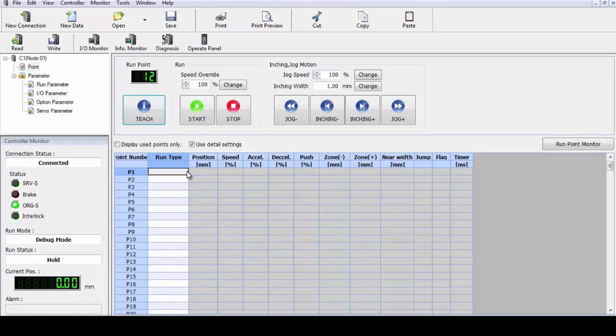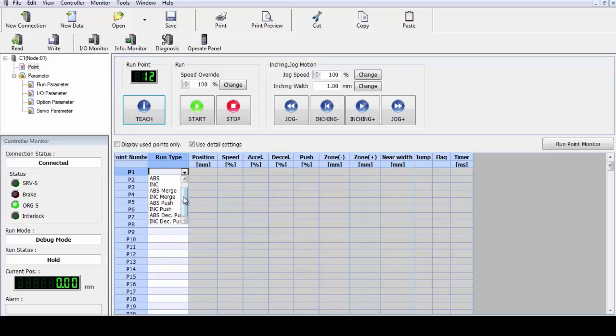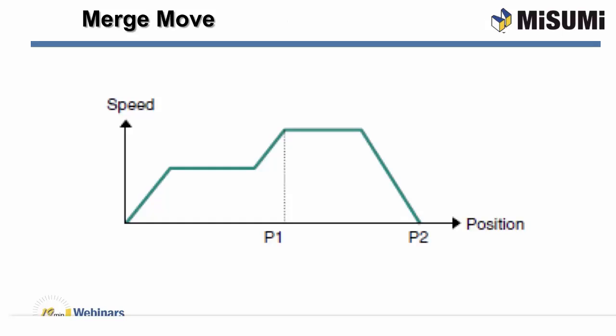Let's go back to our program window and let's take a look at a couple of things we can do. We're going to set up a couple of different run types. We have two different types of run modes that we can be. We can make incremental or we can make absolute moves. If you go down through here, you click on run, it shows all the different moves that are available. Now, on these different moves, you have the standard moves on an absolute or an incremental move. What we do is we accelerate from a zero speed, we come up to speed, and then we decelerate as we approach our position. Depending on the length of the move, you may not achieve full speed and it may be more of a triangular move. But this is a standard for absolute or incremental.